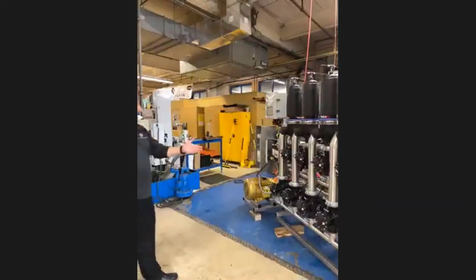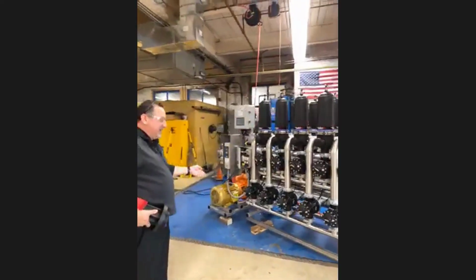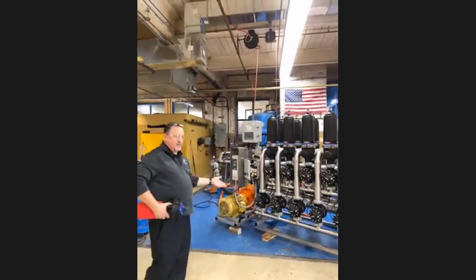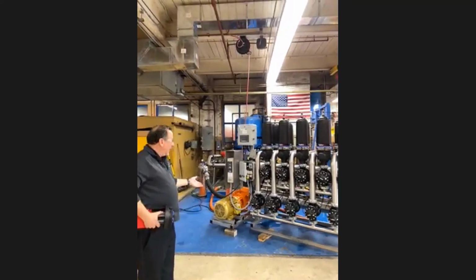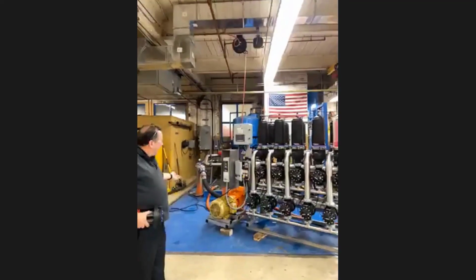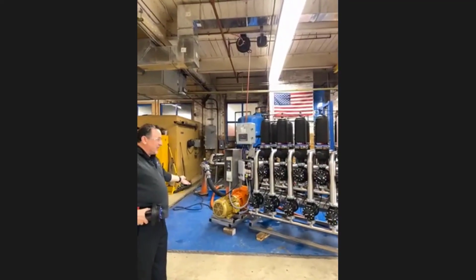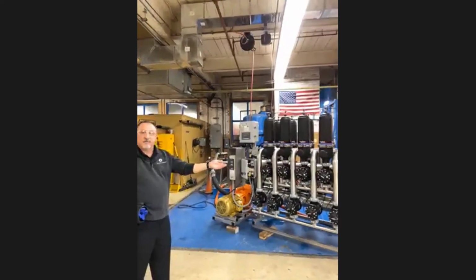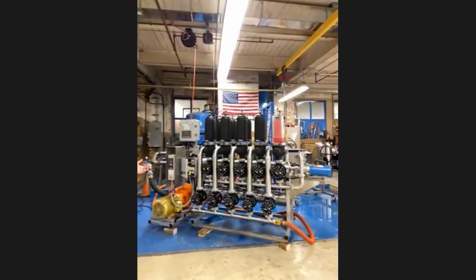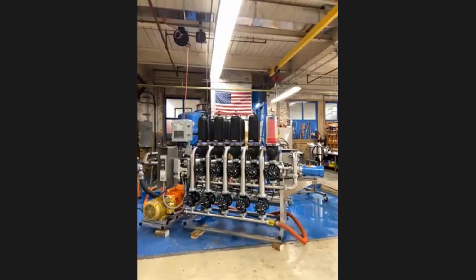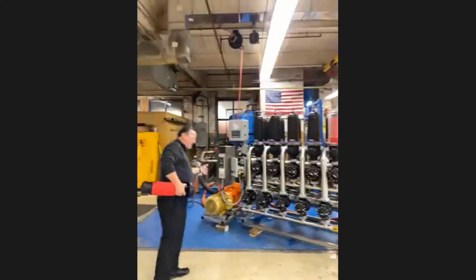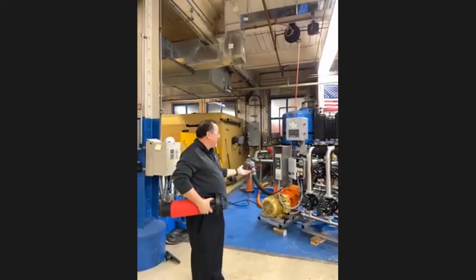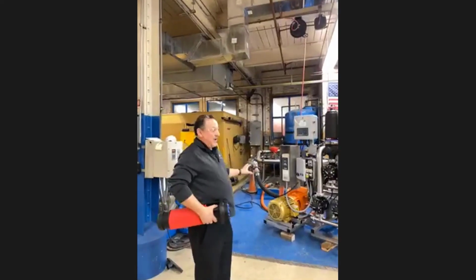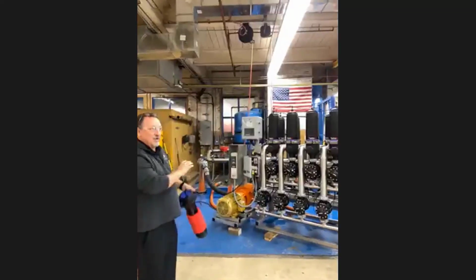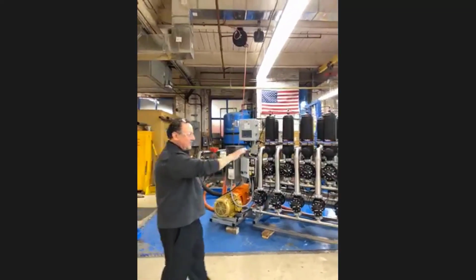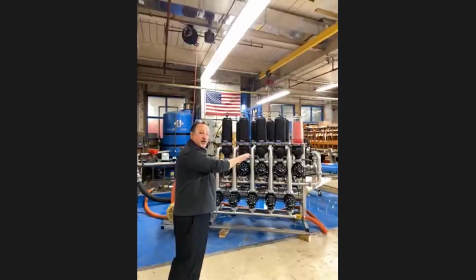So this system right here is 1,000 gallons per minute. It's going to a company up in Minnesota that makes chips. It has a 20 horsepower pump and a 5 horsepower booster pump, which is pretty remarkable for 1,000 gallons per minute. Excuse me. Yes, 1,000 gallons per minute. Had to check and verify that. So with low head pumps, we're only running the flow pump all the time. The booster pump only turns on during a backflush.